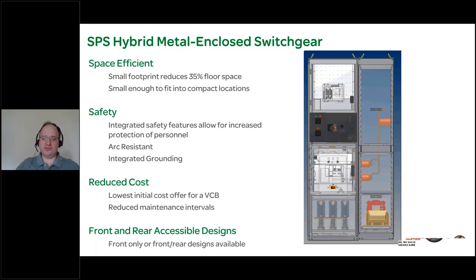We shipped a very similar lineup to this to the largest gray iron foundry in the United States as a temporary solution. It was only meant to be temporary for furnace disconnects while the plant was redoing its medium voltage infrastructure. As part of that plan, these switches were going to be redeployed as the primary of unit substations. Yet the maintenance people so fell in love with integrated grounding that when the time came to move them, they said, "You're not taking these switches from us. These are ours. You can buy another 10 switches for the primaries of your unit substations." So that's how valuable they found the integrated grounding feature to be.